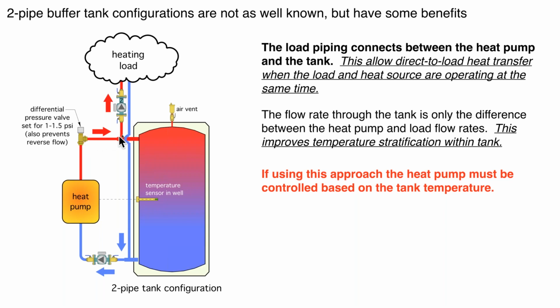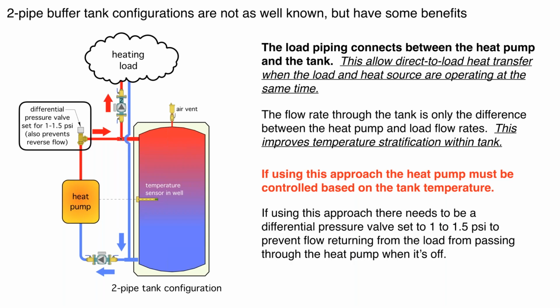And finally, I'll leave you with a detail. If you do this configuration, this header should be as short as possible and keep the pipe size as big as possible. We're trying to minimize any pressure drop through the tank between this T and this T. And if we do that, this configuration will still give us good hydraulic separation. Okay? So don't take this T and put them 50 feet away from the buffer tank. That's going to build up more differential pressure in this portion of the circuit, and we're starting to lose this beneficial effect called hydraulic separation.